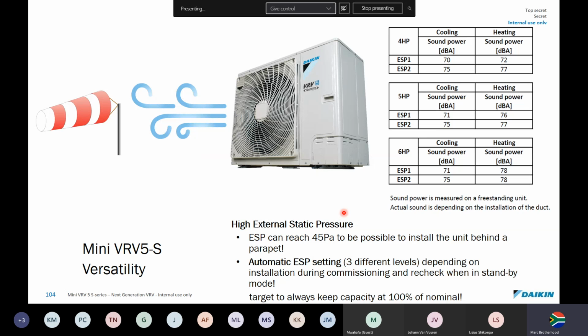Ironically, on the other side of things, we can also increase the ESP on these fans. So external static pressure can reach 45 pascals. So the good thing is you can put a little duct cowling on here to push the air through. There's 3 different settings. The ESP pretty much means external static pressure, and what that means is the work that the fan has to do to move a volume of air. That's put simply.